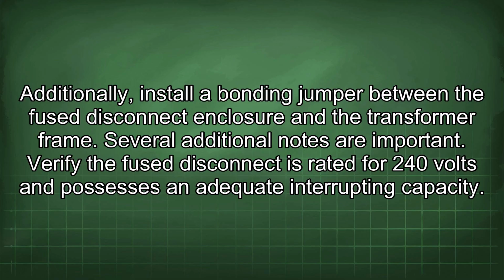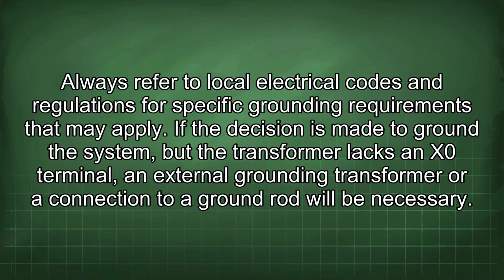Several additional notes are important. Verify the fused disconnect is rated for 240 volts and possesses an adequate interrupting capacity. Always refer to local electrical codes and regulations for specific grounding requirements that may apply. If the decision is made to ground the system but the transformer lacks an X0 terminal, an external grounding transformer or a connection to a ground rod will be necessary.